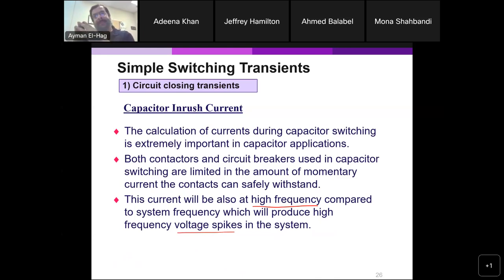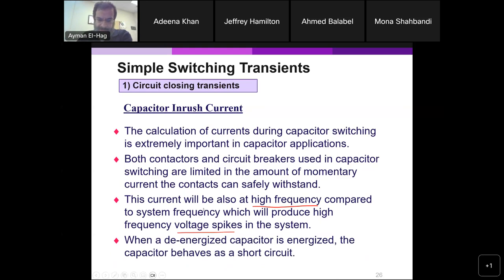Now, in distribution systems, the main factor that decides the surge protection is lightning, because switching is much less severe than lightning. However, for transmission equipment, it's the opposite: switching is more severe than lightning. So when we energize a capacitor, it behaves as a short circuit. We mentioned that before. Whenever I energize a de-energized capacitor, it will first act as a short circuit, and then it will eventually be charged.